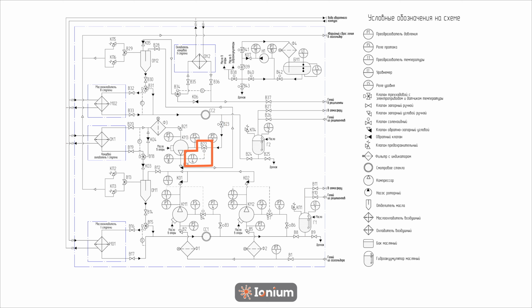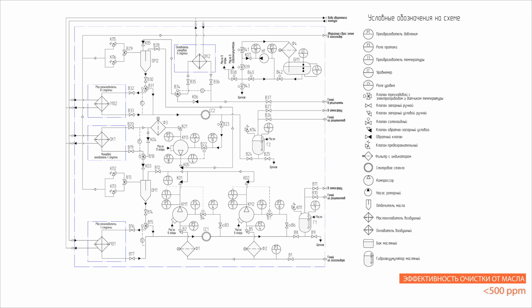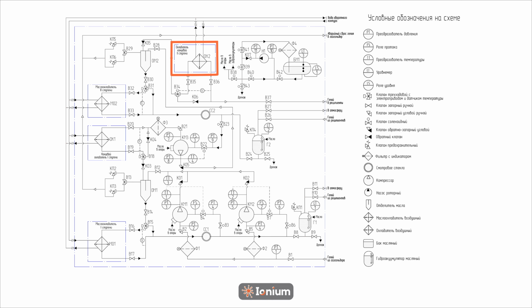The oil flow is determined by the helium outlet temperature, using the TT4 device from the KM3 compressor, and regulated by the V22 flow controller. Helium purified to a mass concentration of about 500 ppm is directed to the OH2 water-helium heat exchanger, where it's cooled to around 28 degrees Celsius by the recirculating water from the air cooling unit. Additional helium cooling is recommended, cooling it to about 16 degrees Celsius, using the chiller's intermediary circuit water in the water-helium heat exchanger, cooled by the evaporators of the vapor compression refrigeration system.